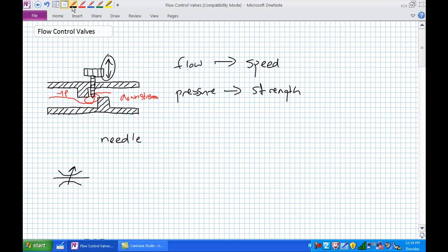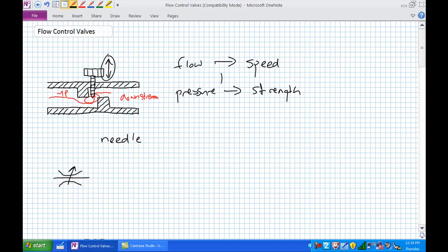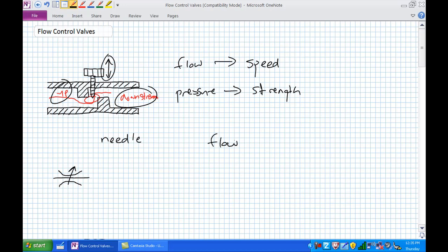Flow equals speed, pressure equals strength — and one would assume there's a brick wall between those two concepts. But there is a little bit of interaction between them, especially inside flow control valves. A flow control valve requires a pressure differential between upstream and downstream to work. Typically, a manufacturer will give you the flow rate per psi of differential across the valve.